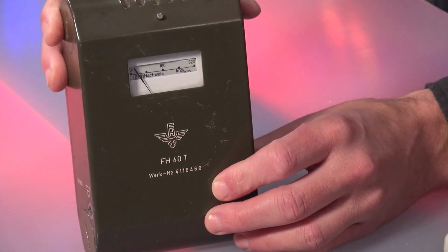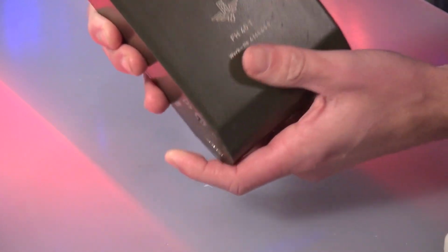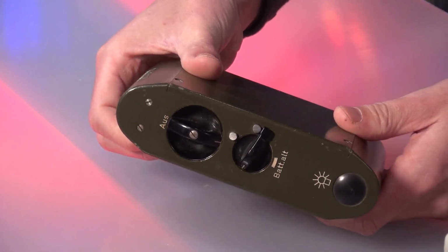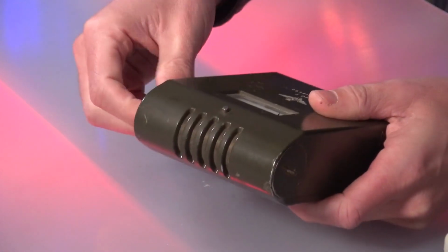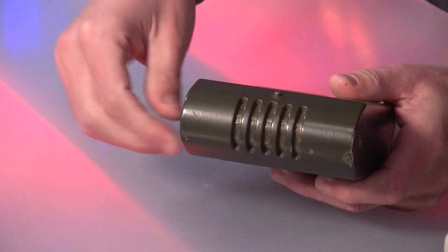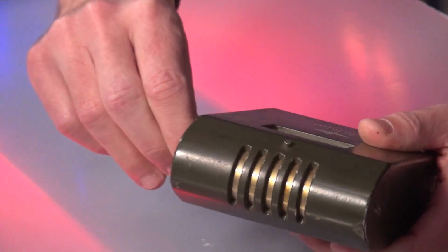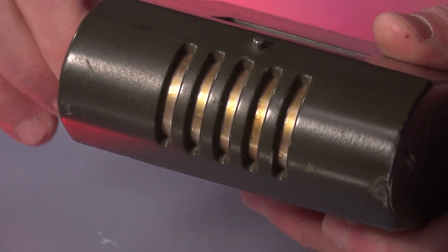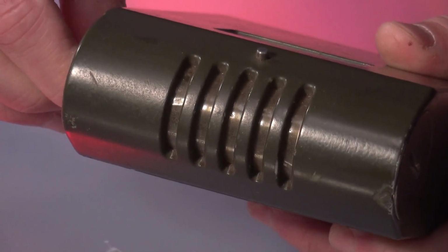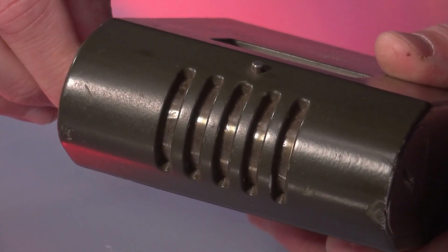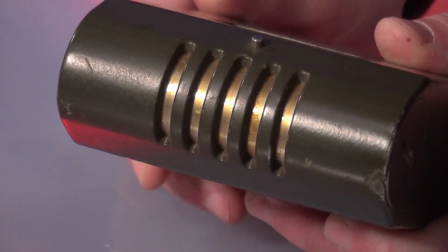And we also have the option of setting different modes. The switch is on the side, and what I want to show you is up here. If you look into the slots there, we can say we only want to measure the gamma radiation. And if I go back again, beta radiation, gamma radiation together, and only gamma radiation, there is suddenly a shielding over here, which is because the gamma radiation can penetrate this shielding.